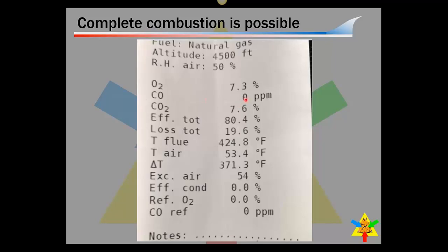but the key thing to take away from this is look at your CO production. As measured, 0. CO air-free, 0. This is complete combustion. There is no carbon monoxide in this. So it can be done. And this is a great tape. That's what we like to see.